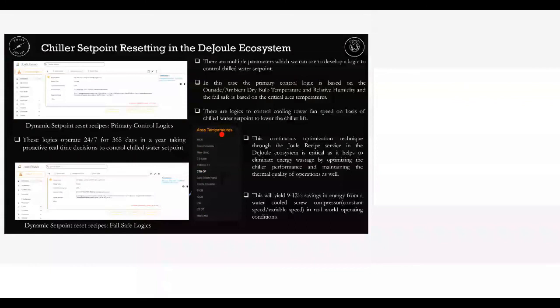At the same time, the IoT senses that there is a bottleneck or problem area. As the temperature goes high, it will activate the fail-safe. First, it increases the fan speed of the heat exchanger in the blower fan, then it opens the valve, facilitating more water flow, up to 100%. If the problem still persists, we reduce the chiller set point and increase the chilled water pumping. So all these fail-safes are in place.